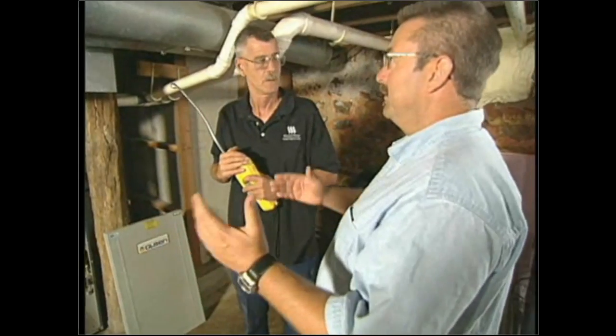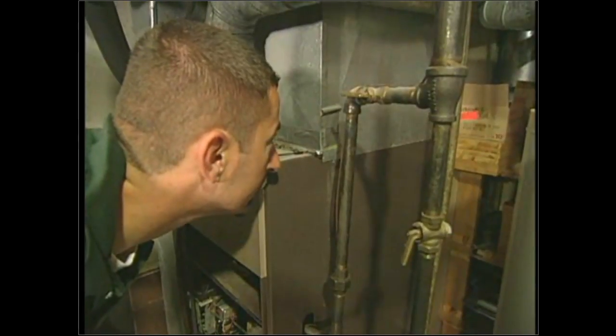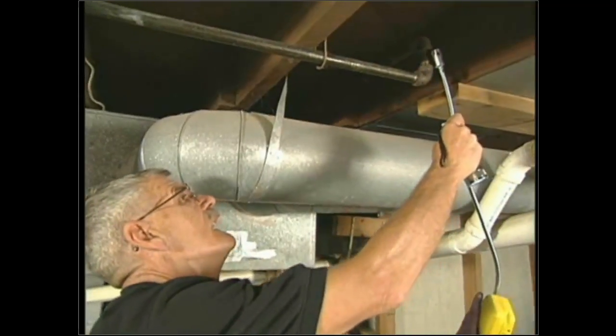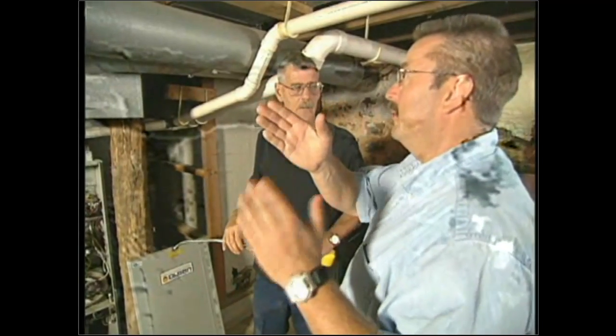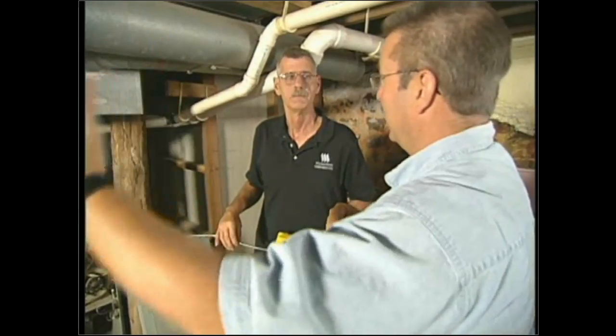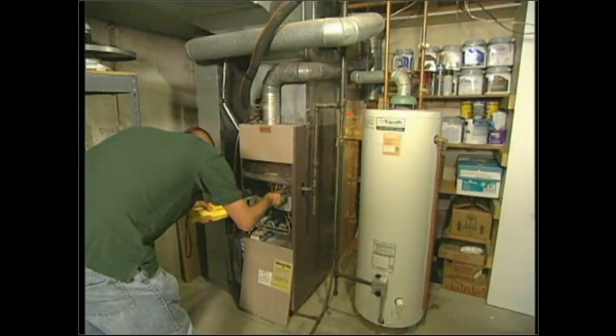Is it possible to say where you typically find more gas leaks? You want to look at valves, check unions, and where they have short tight nipples or short connectors — because it's hard to get those torqued in properly. But at the end of the day, from an auditor standpoint, whether you start at the furnace, the meter, or the regulator — check every single connection. You have to check every connection because you don't know what you're going to walk away from.